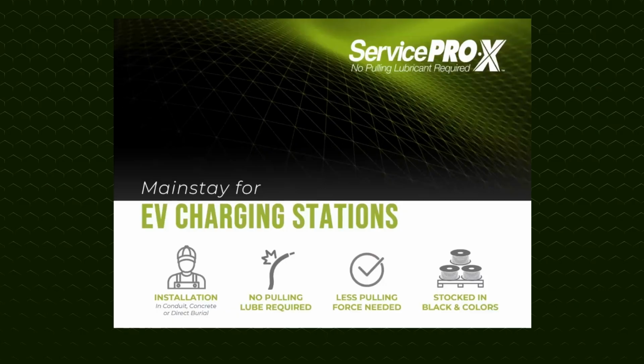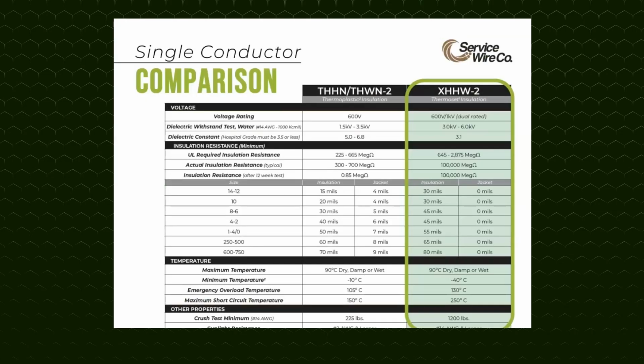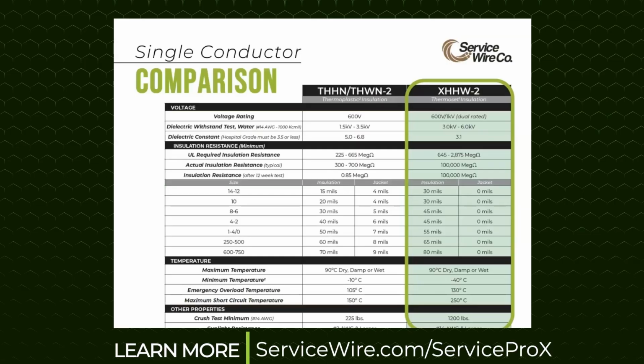In fact, one of our most notable EV projects was won through in-stock black and red 250, 300, and 500 MCM XHHW2 Service Pro X single conductors. Hundreds of miles of our cable was run underground in conduit from the transformer and switchgear into individual charging stations. All Service Pro X single conductors are manufactured with crosslink polyethylene XLPE insulation instead of PVC nylon. Thermoset XLPE insulation is more resistant to chemicals, abrasions, and leakage current, and has far superior electrical performance characteristics than thermoplastic products like THHN.